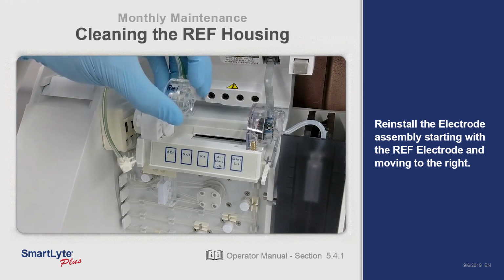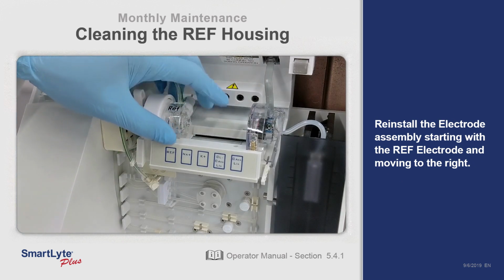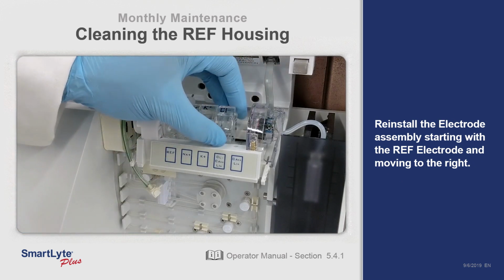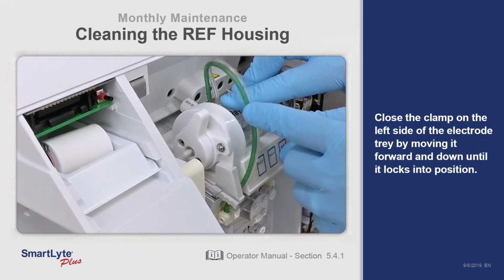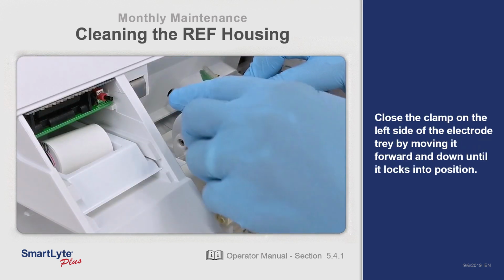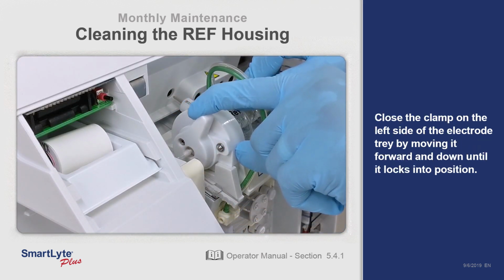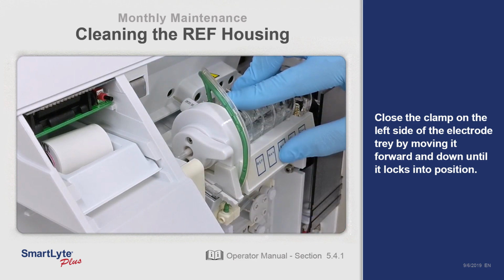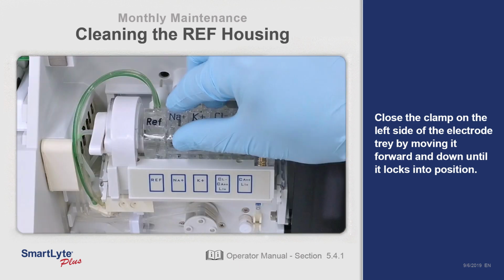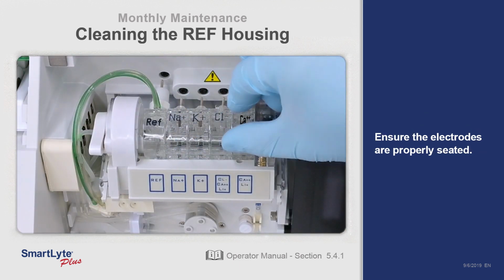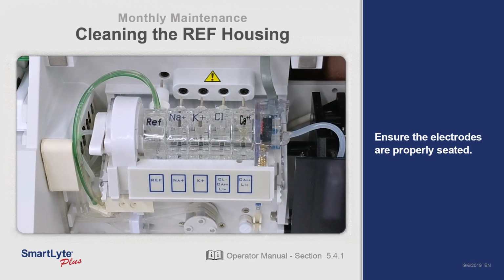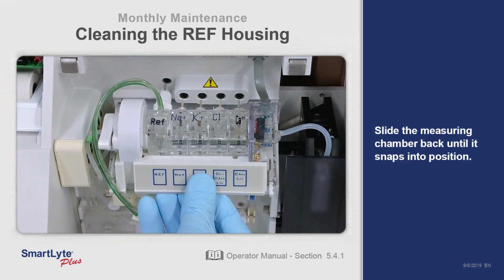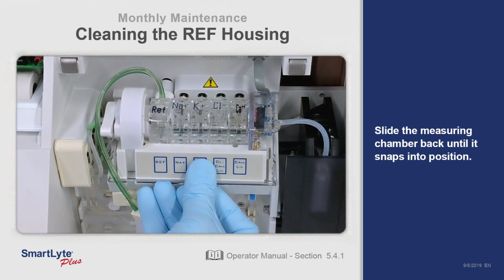Reinstall the electrode assembly, starting with the reference electrode and moving to the right. Close the clamp on the left side of the electrode tray by moving it forward and down until it locks into position. Ensure the electrodes are properly seated. Slide the measuring chamber back until it snaps into position.